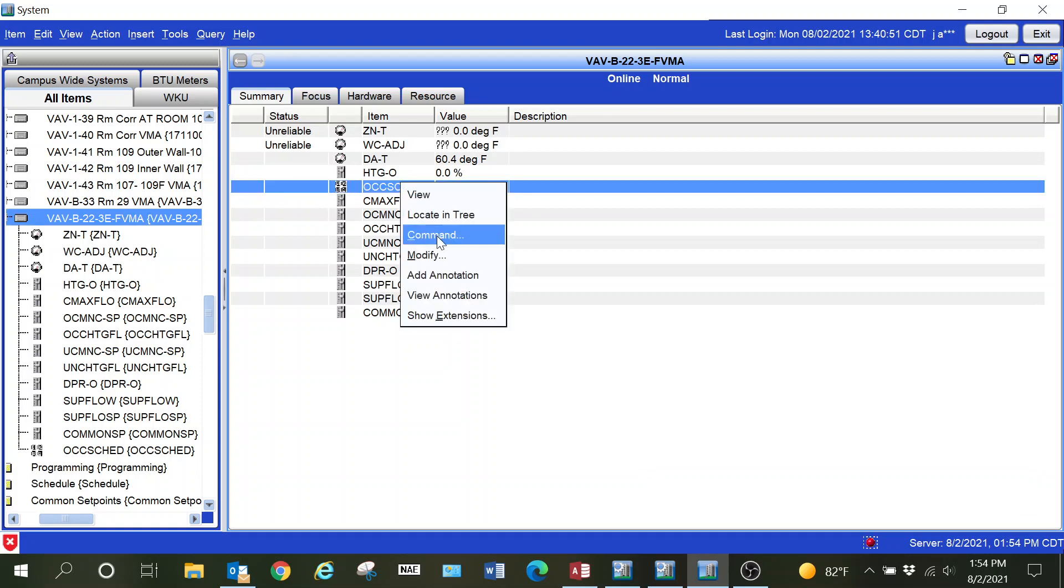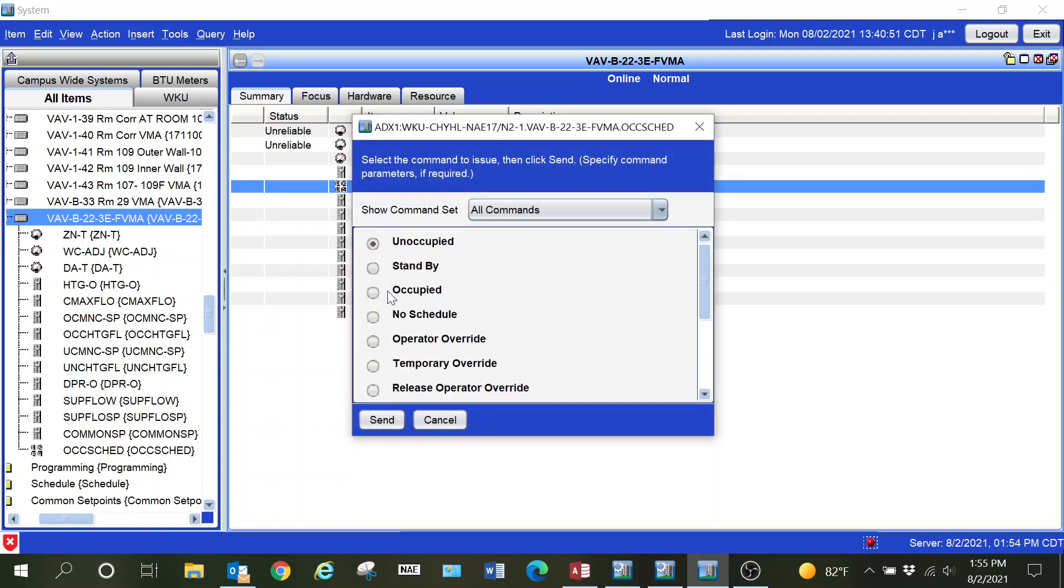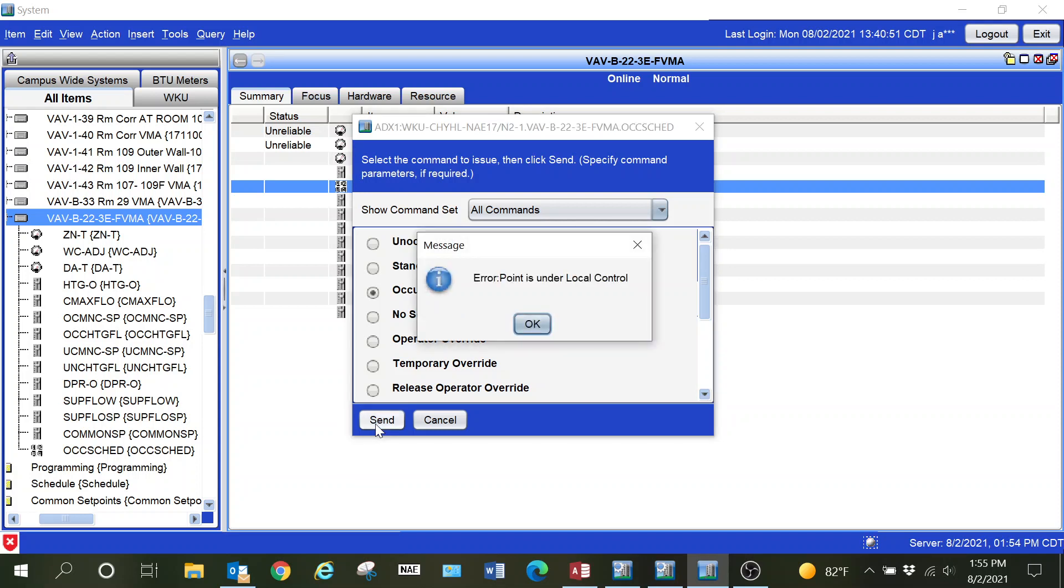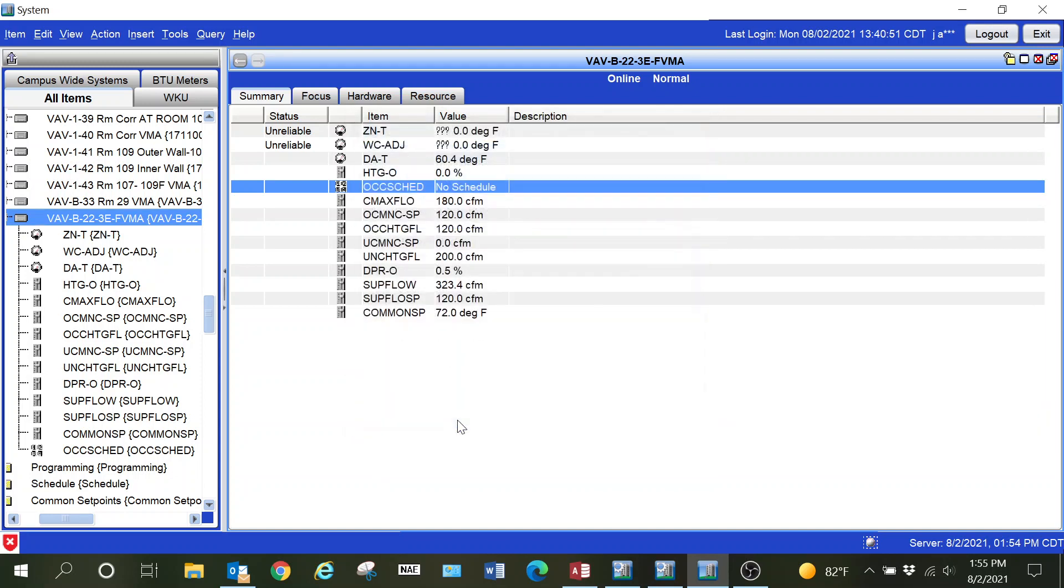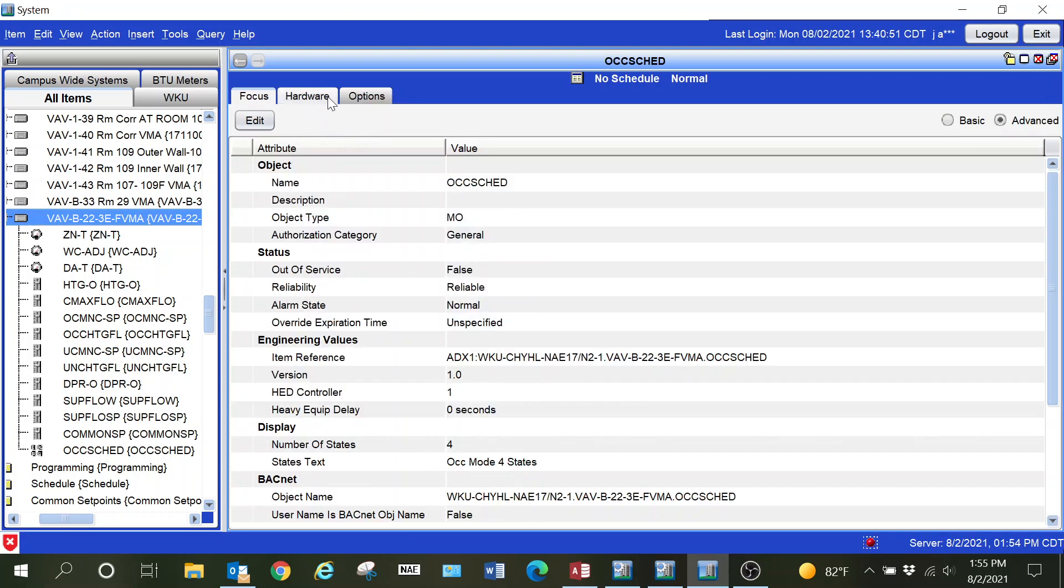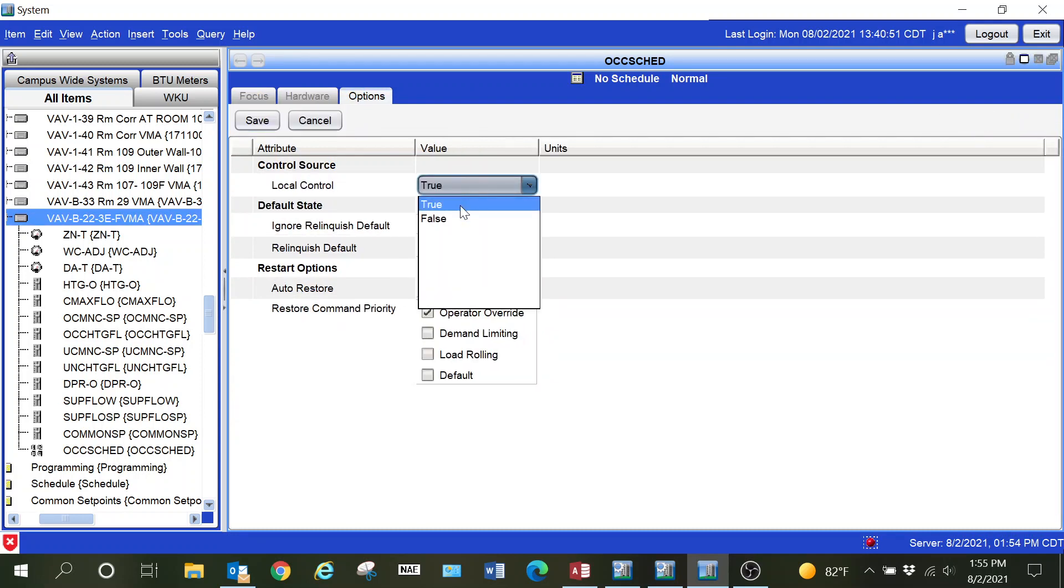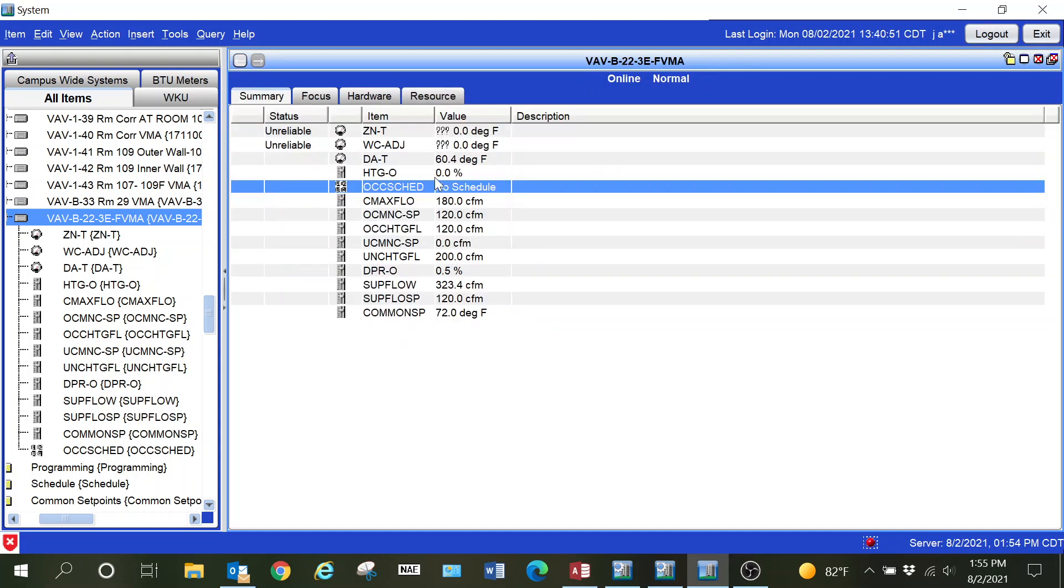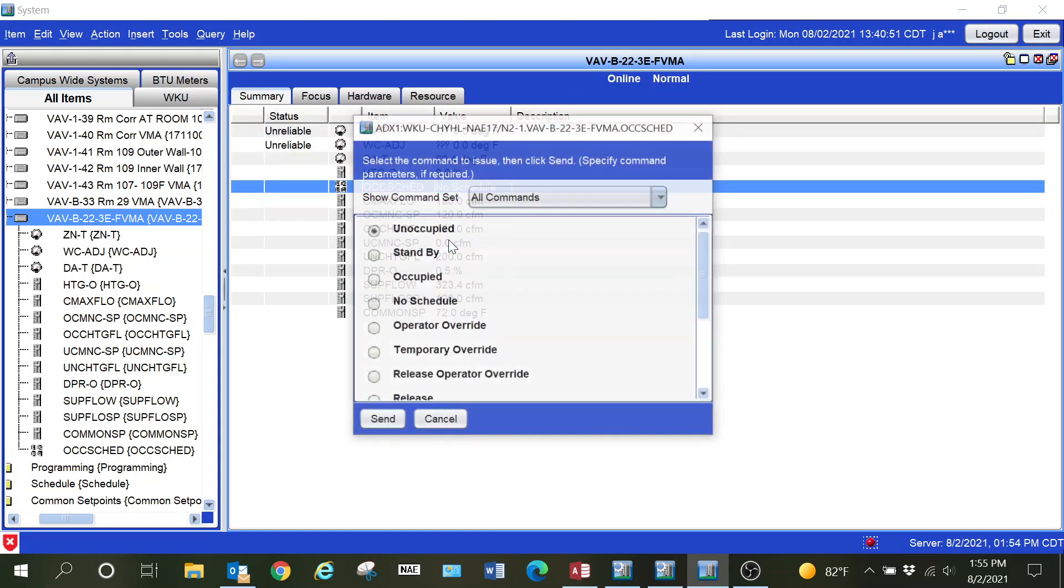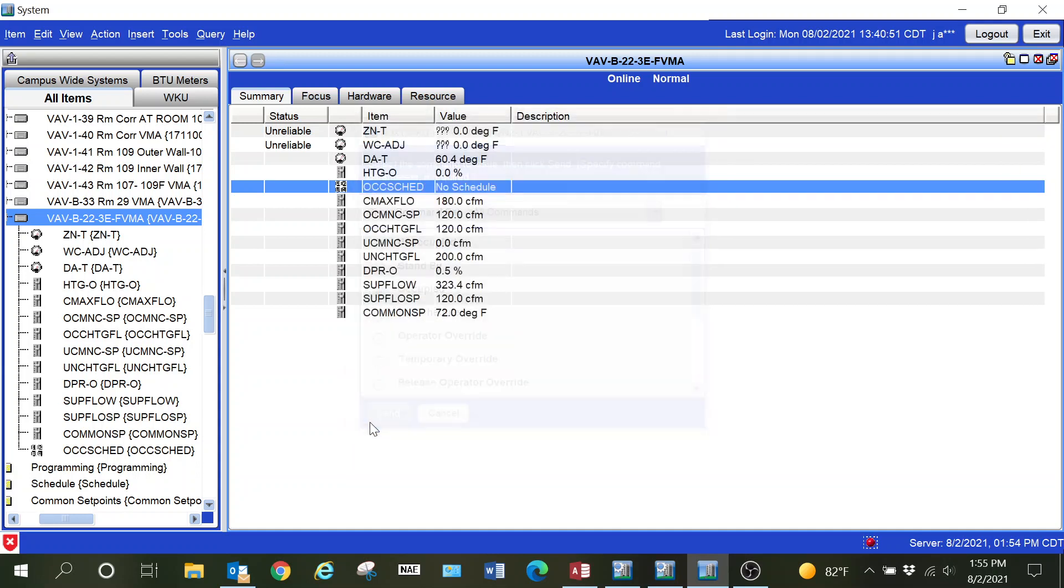There is our state text. Now when I go to change it to occupied, it gives me this error: point is under local control. The way that I can change that is simply go into view that point, go into the options tab, select local control and set it to false. Then when I hit save, I can go back and do a normal command on that point.